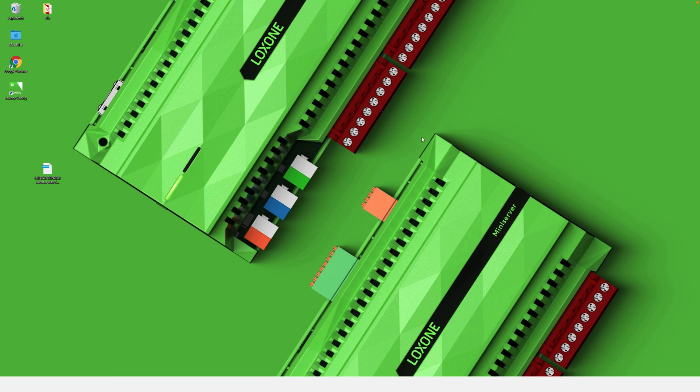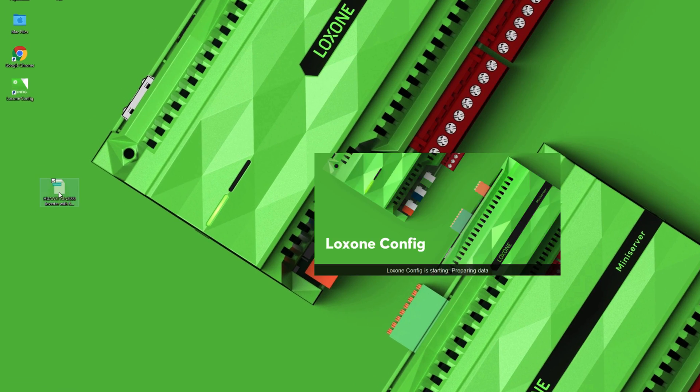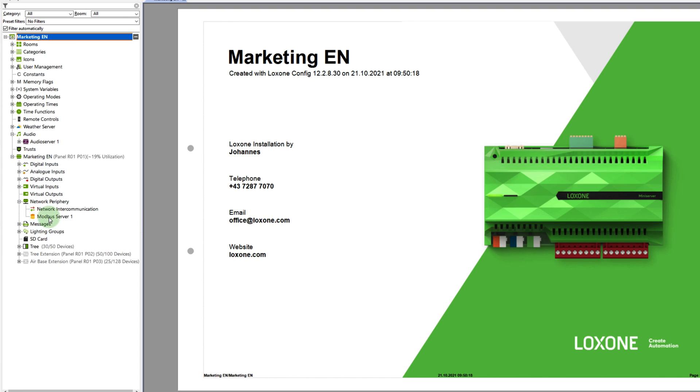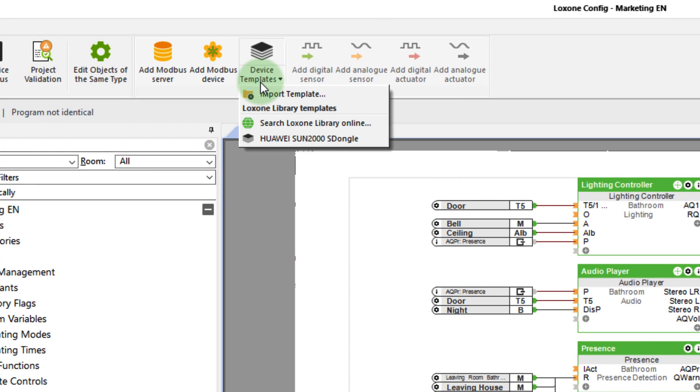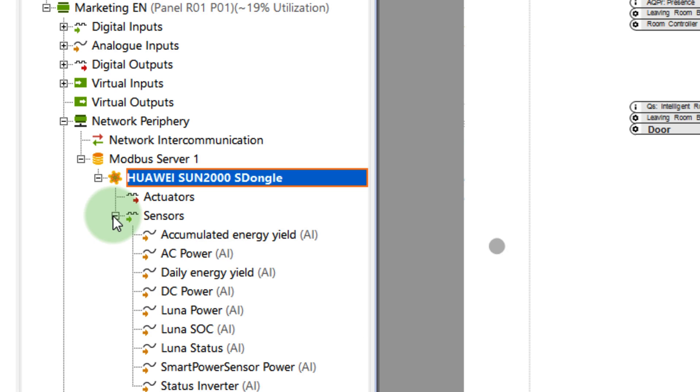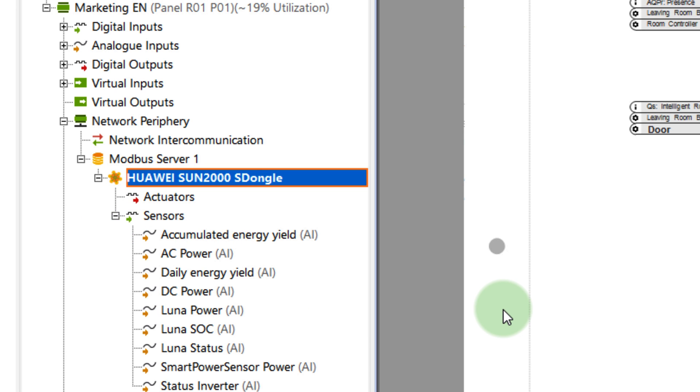I won't keep you waiting much longer. Let's have a look at the new Loxone Library in detail. By double-clicking on the downloaded file, the template is added. In my case, the inverter communicates via Modbus TCP, so via the network. That means I have to create a new Modbus server network device and can now open the template under the Device Templates option. And with just those few clicks, all stored inputs and outputs are available.